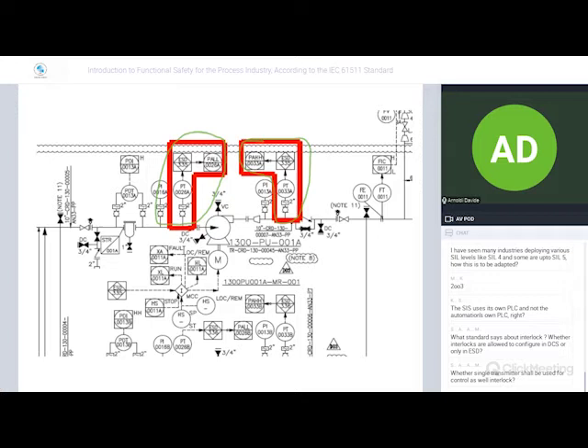Why? Because the problem was this manual valve. In case of a mistake by the operator to close this valve, the pump could be broken due to the high pressure. So, during the SIL allocation, we define to install a new function in order to protect the pump from the high pressure.